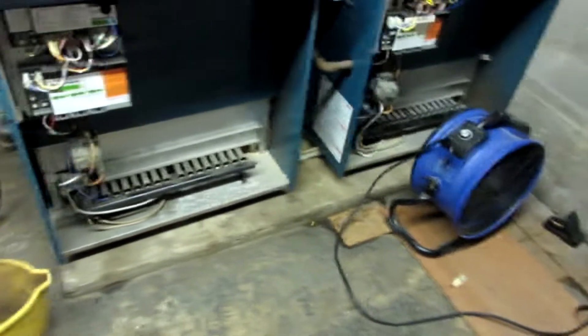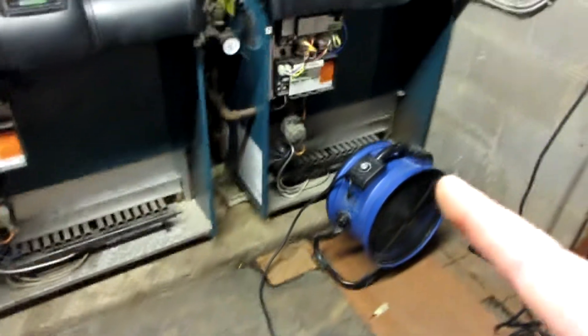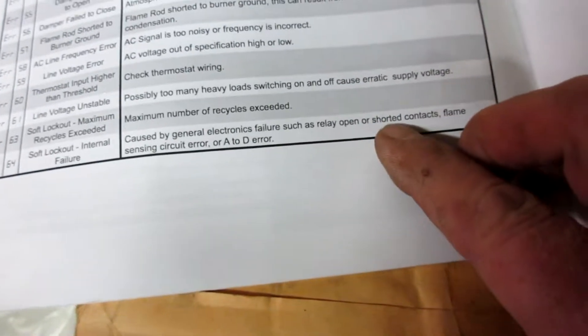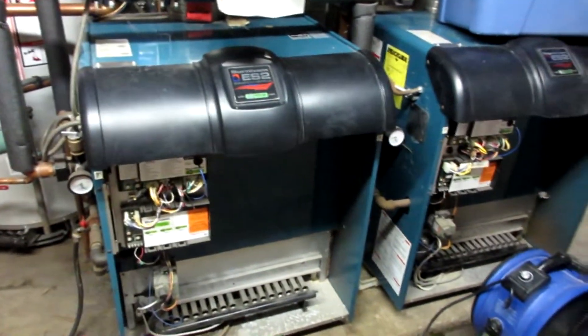When I turn them back on after they sit for 10-15 minutes, this one is throwing a different error — error 64 — which says: soft lockout, internal, caused by general electronics failure such as a relay open or shorted contacts, flame sensor circuit error. So I need to get some heat in this building.